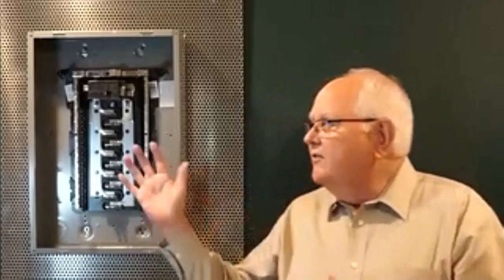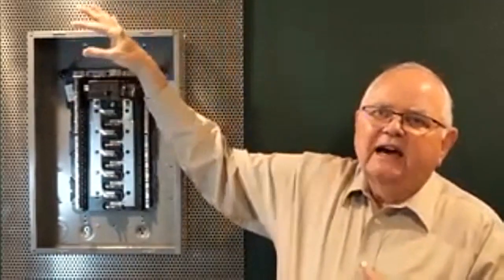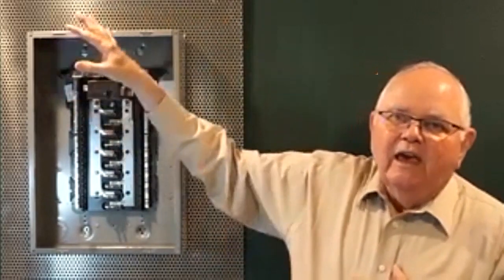Now let's get down to work. Let's say that our job was to go out and pull the cover off of this panel, make sure that it's all de-energized. Maybe it could be a service panel, but let's say it's a sub panel and it's being fed upstream from a feeder breaker. So we have already locked out and tagged out that feeder breaker, and now we're going to come in and verify that this panel is in fact de-energized, that we got the right breaker upstream, and then we can do the work on the buses as we need to replace breakers or whatever it is we're going to do then.